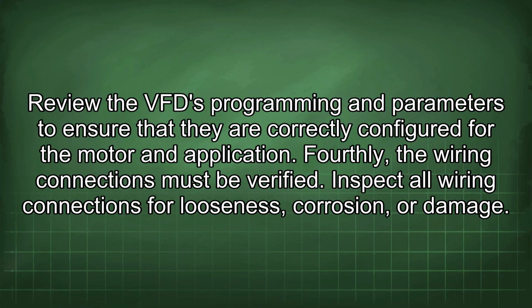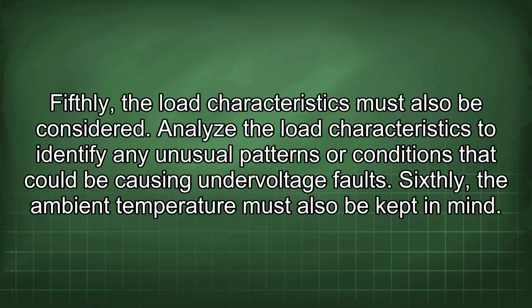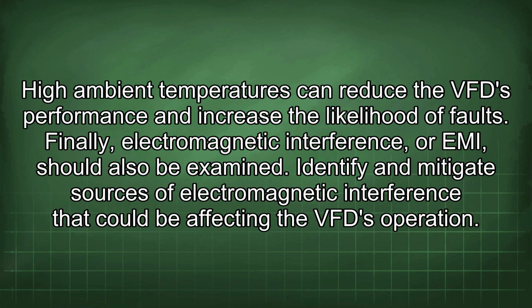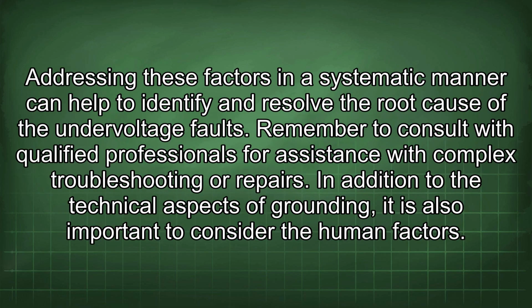Fourthly, the wiring connections must be verified. Inspect all wiring connections for looseness, corrosion, or damage. Fifthly, the load characteristics must also be considered. Analyze the load characteristics to identify any unusual patterns or conditions that could be causing undervoltage faults. Sixthly, the ambient temperature must also be kept in mind. High ambient temperatures can reduce the VFD performance and increase the likelihood of faults. Finally, electromagnetic interference, or EMI, should also be examined. Identify and mitigate sources of electromagnetic interference that could be affecting the VFD operation. Addressing these factors in a systematic manner can help to identify and resolve the root cause of the undervoltage faults. Remember to consult with qualified professionals for assistance with complex troubleshooting or repairs.